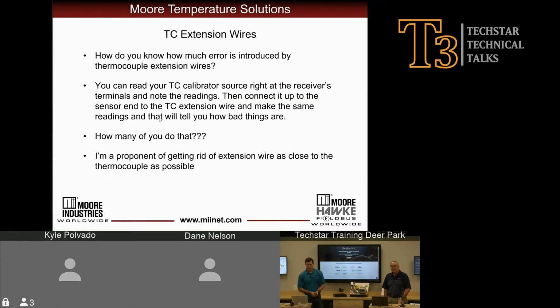So one question that I ask is how do you know how much error might be introduced by a thermocouple extension wire, or do you check the thermocouple extension wire? Thermocouple extension wire can fail just as thermocouples can fail, or as we discussed in the previous slide, thermocouple extension wire could corrode and induce error into your temperature measurement over time. So there's ways that you can check the error in your thermocouple extension wire and your thermocouples by reading your thermocouple calibrator at the receiver terminals and noting the reading. You then connect it up to the sensor end of the thermocouple extension wire, and you can make the same readings, and it'll let you know how bad things are.